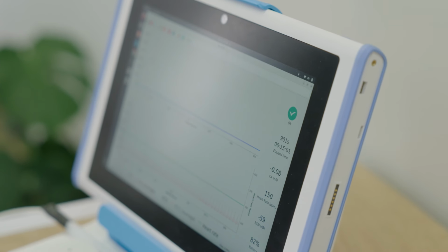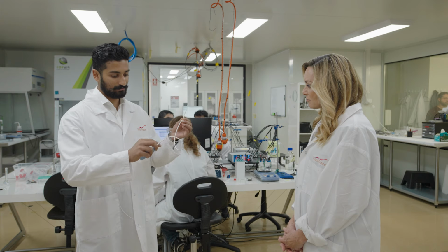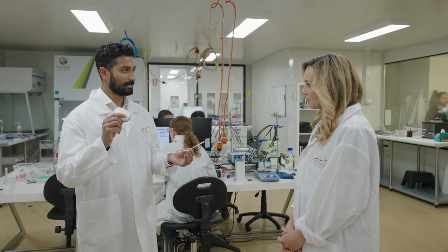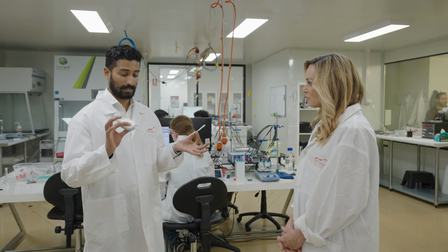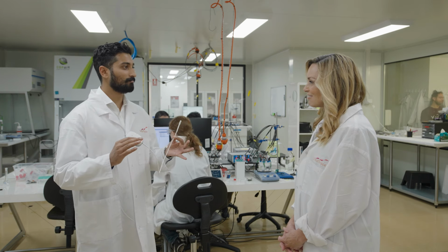with these incredible biosensors. So the way this would operate is very similar to an existing device called a scalp electrode. It's inserted onto the baby's scalp through the birth canal, and from there a single lead leads to the mother's leg, where this wearable is worn by the mother. Now what's different about this is that's it. The mother would be able to move around, squat, shower, move around in labour naturally, and the doctors will get world-first data of lactate and heart rate in real time.